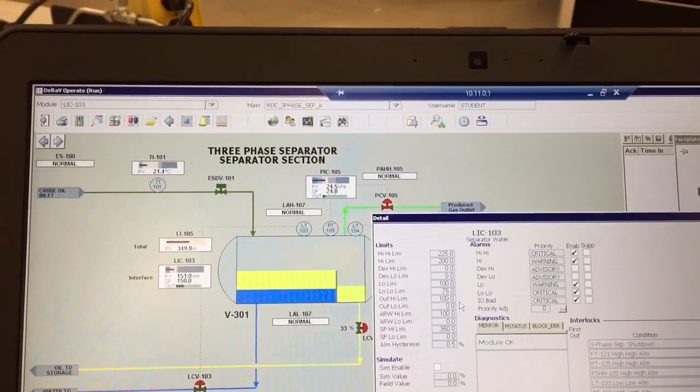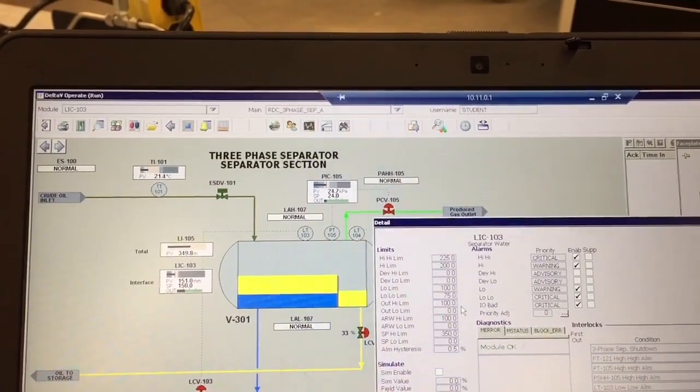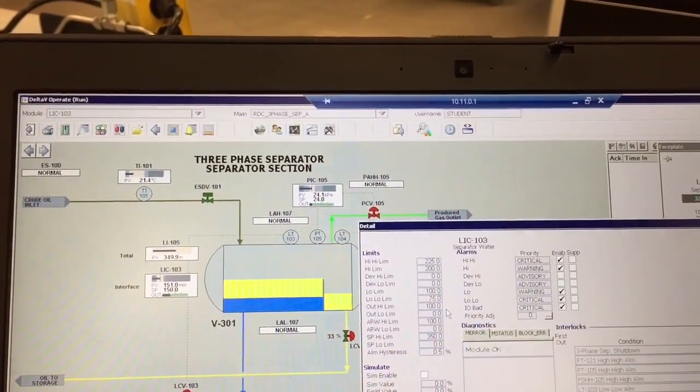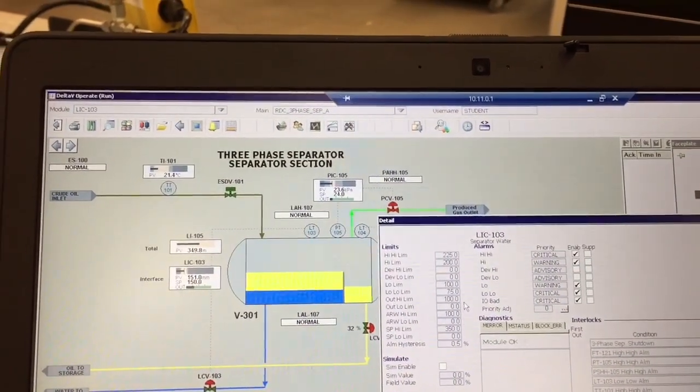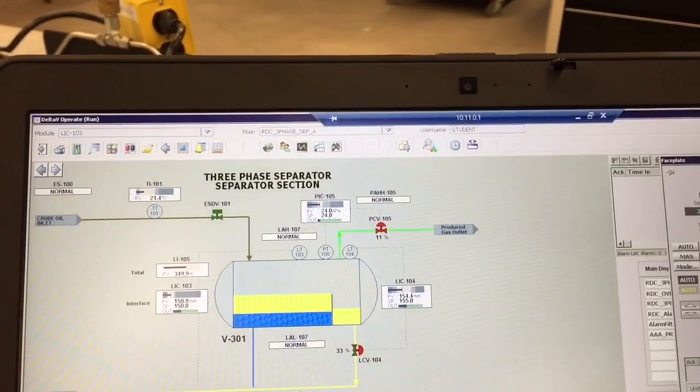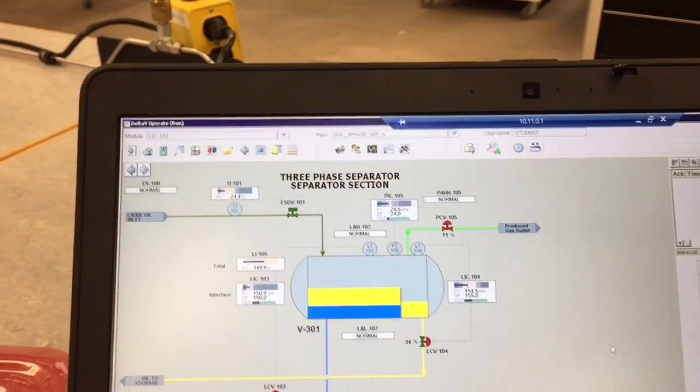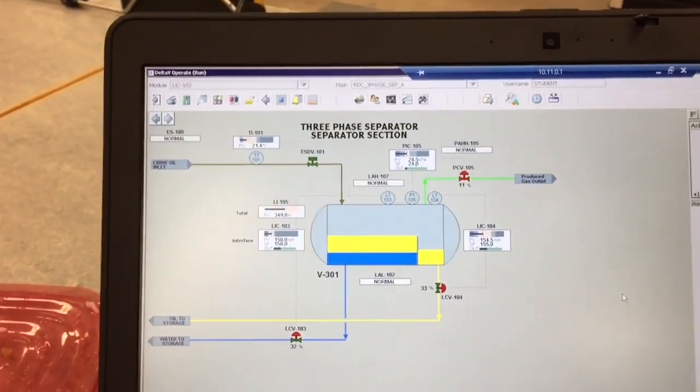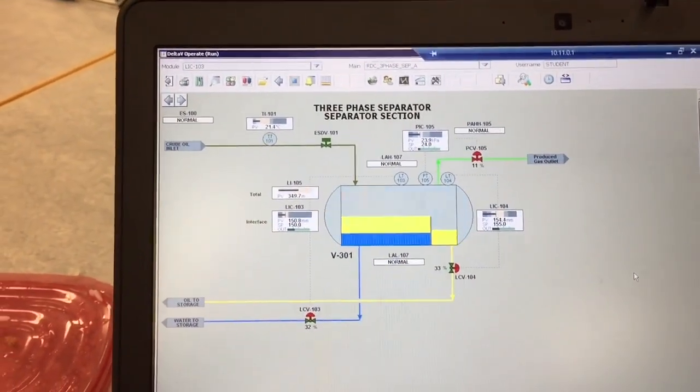And if we go down too low, it'll see the end of the probe and that tends to mess up. Our process will shut down on a low level just so we don't have any oil going into our water tank. So probably one of the slowest loops on our process out of all of our trainers as well.